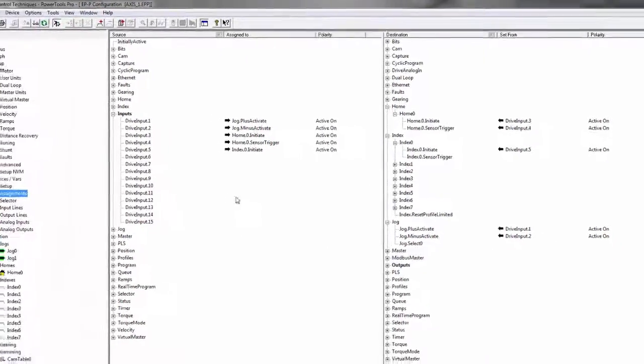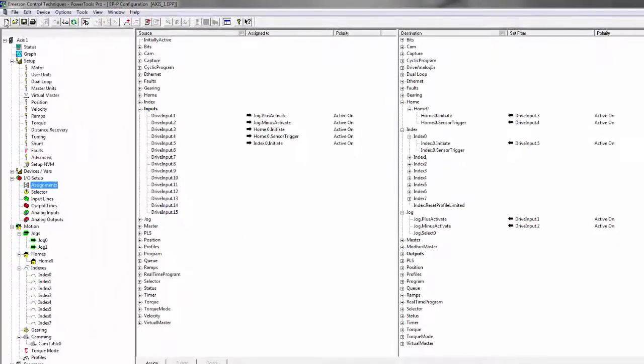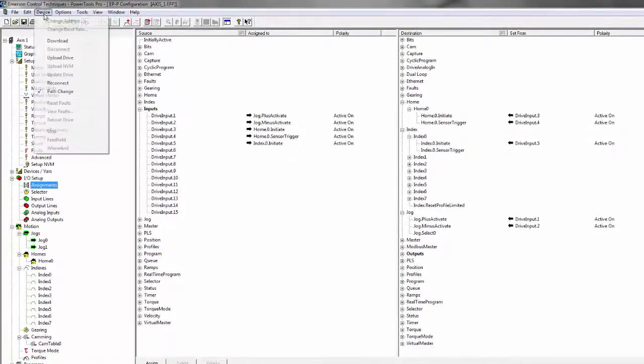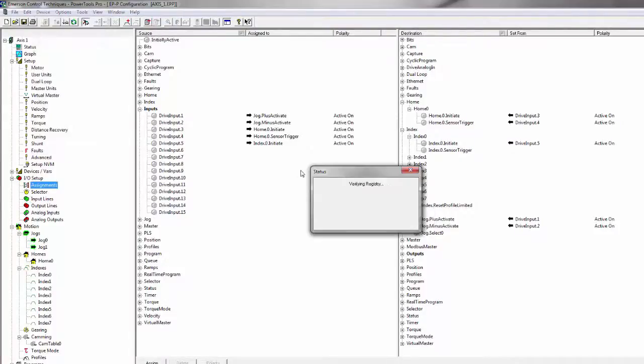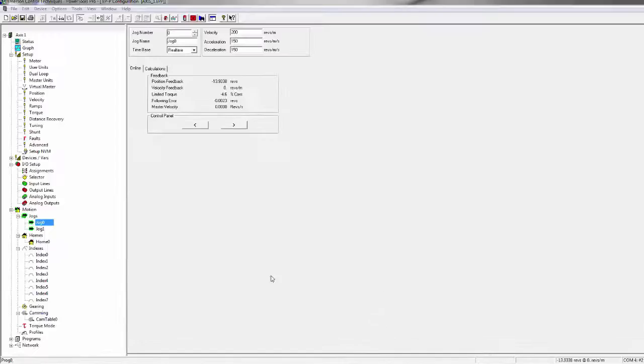Okay, now that inputs are assigned we're ready to download this and give it a try. We'll go to device and download. We'll look for the drive and download. Now that we've downloaded, you can see we're online. I get my actual signal saying we're connected and my actual position feedback. So if I want to try this out before anything is wired I can do that.